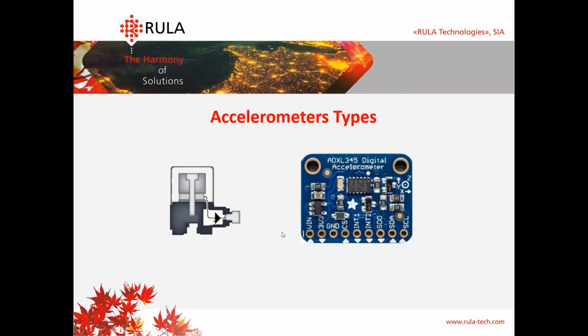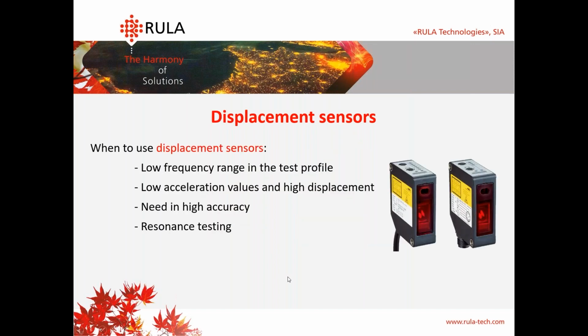In our software, we can connect 2 accelerometer types. We can use regular piezoelectric accelerometers or MEMS accelerometers. Also, we can run our tests with displacement sensors. We need to use them when we have a really low frequency range in the test profile. We have low acceleration values, but high displacement values. And if you need high accuracy, it's good to use these displacement sensors during resonance testing, because they don't influence the object mass. So you'll get the correct values during the test.